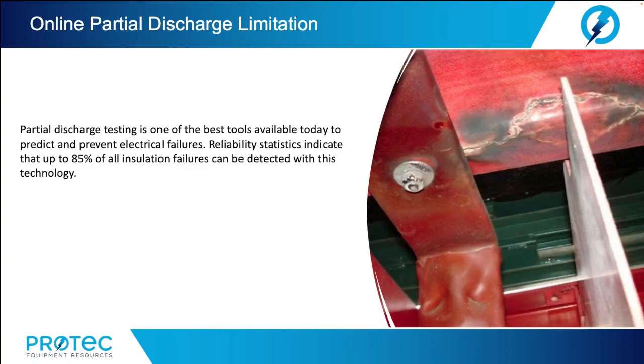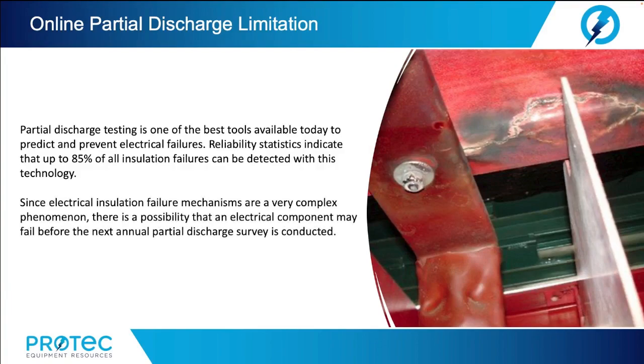Partial discharge testing is one of the best tools available today to predict and prevent electrical failures. Reliability statistics indicate that up to 85% of all insulation failures can be detected with this technology. Now, since electrical insulation failure mechanisms are very complex phenomena, there is a possibility that an electrical component may fail before the next annual partial discharge survey is conducted.